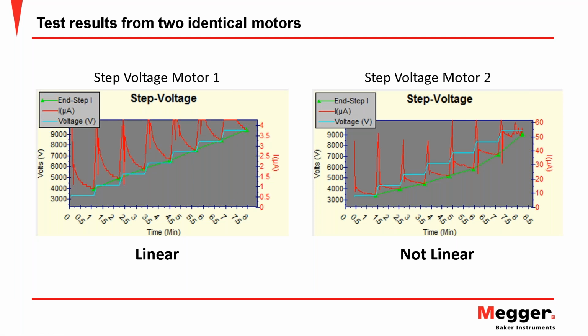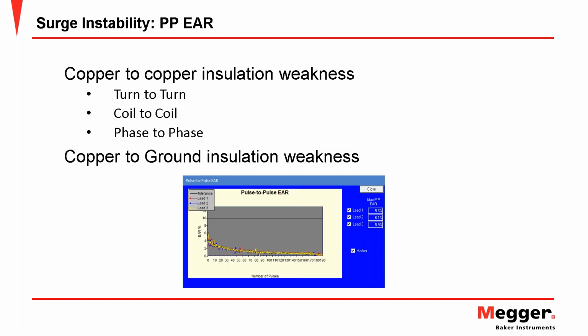And the other interesting feature in this particular graph is the erratic current that occurs at the highest voltage level of around 9,200 volts there. And so I would bet that if I tried to go an additional 1,000 volts, that motor probably would fail on over current. And so I know exactly where I am on the breakdown curve, you know.